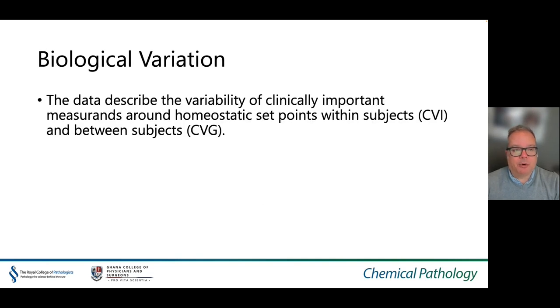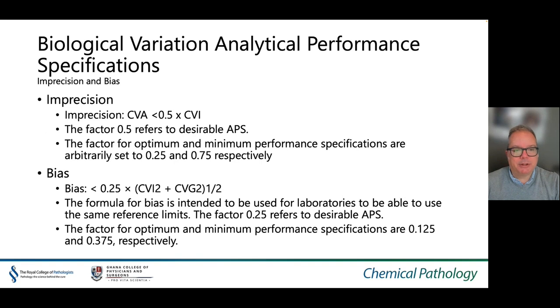Biological variation is one of the most useful ways of setting analytical performance specifications. Biological variation data describes the variability of clinically important measurands around homeostatic set points — within-subject CVI and between-subject CVG. This data can then be used to set analytical performance specifications. In the case of imprecision, the imprecision target CVA (the analytical CV) should be less than 0.5 times CVI. The 0.5 refers to the desirable analytical performance specification, while optimum and minimum performance specifications are arbitrarily set to 0.25 and 0.75 respectively.